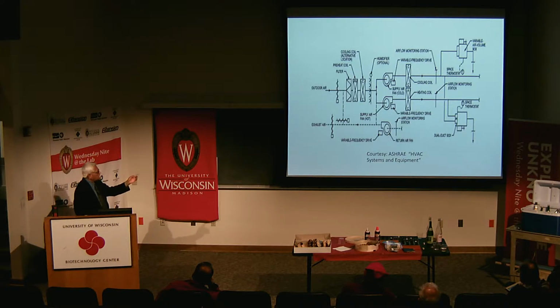So you need a blend of this hot air as well as cold air. That's why this box is called dual duct variable air volume boxes. So you have one cold air line going through, another hot air going through. You have got a damper here which modulates the amount of cold air that goes into the room and the amount of hot air that goes in the room.